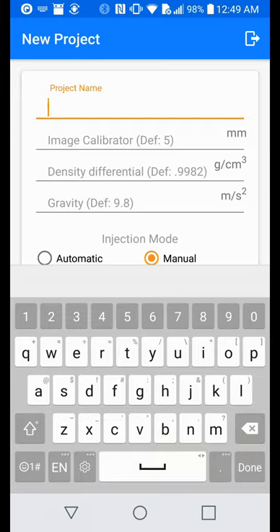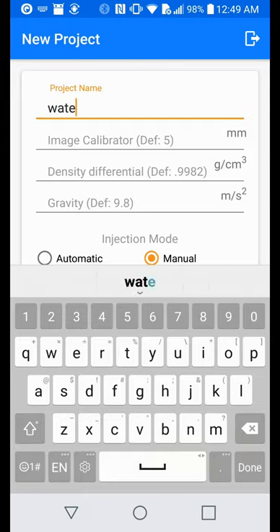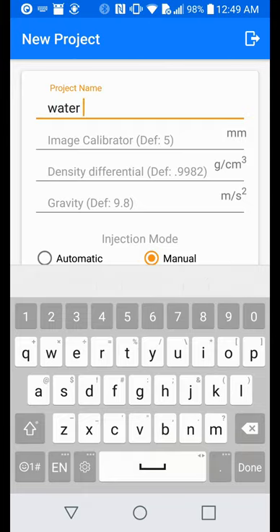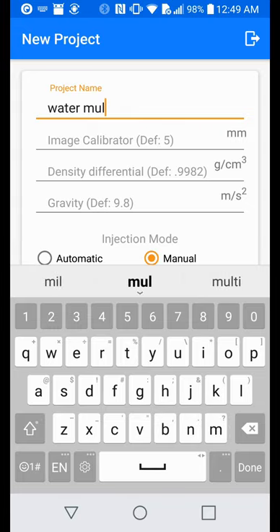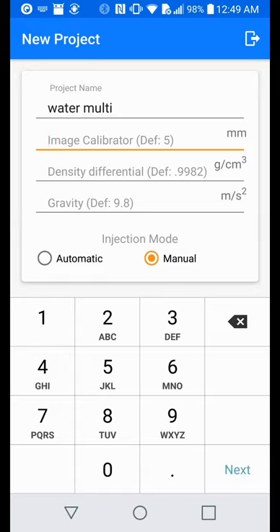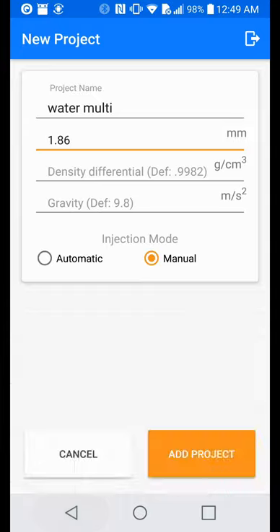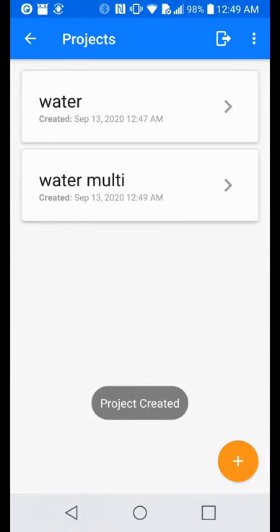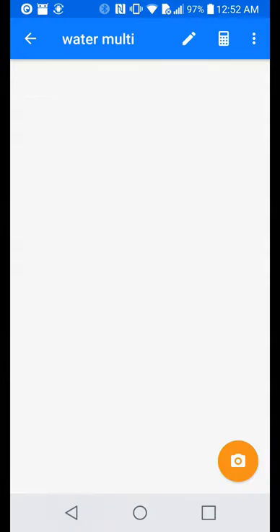The app's multi-capture function can also be used to take multiple images in a set timeframe. This can be used as a foolproof way of measuring the surface tension by generating the droplet slowly, and taking the image right before it detaches from the needle. It can also be used to measure the dynamic surface tension of a liquid.